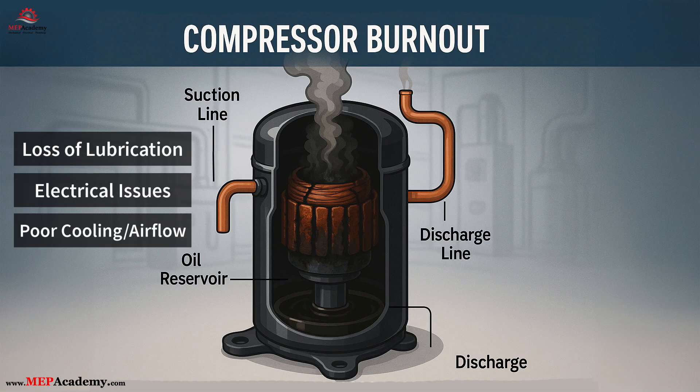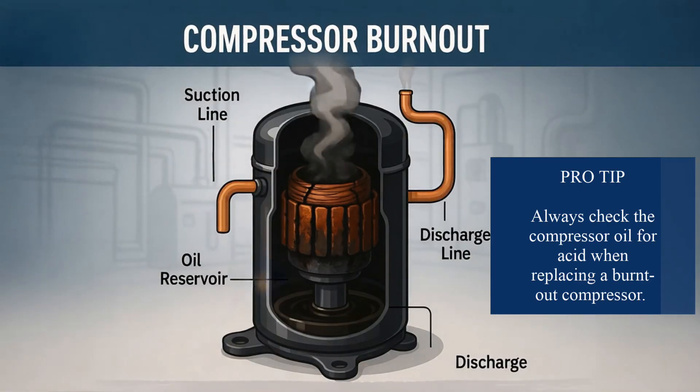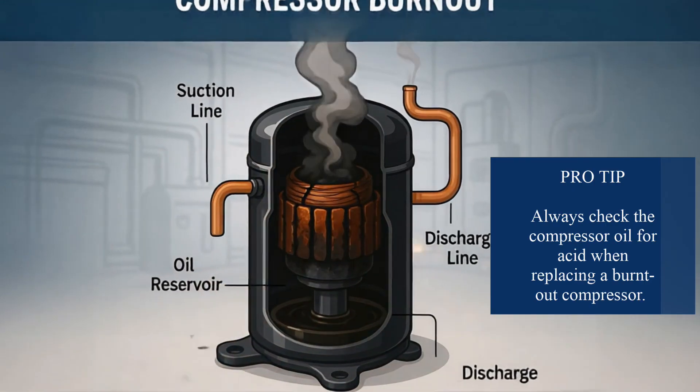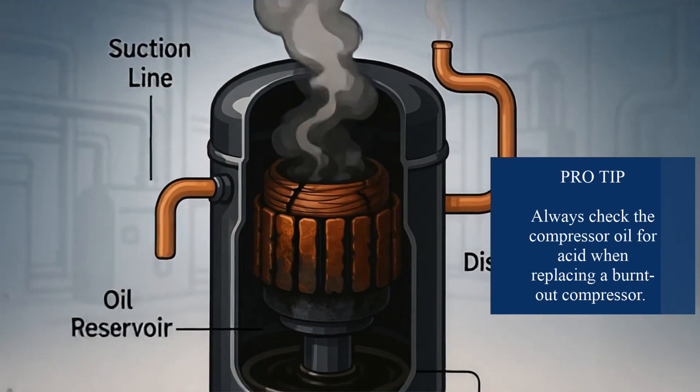Overheating due to poor cooling or airflow occurs when dirty condenser coils, blocked airflow, or failed condenser fans prevent proper heat rejection, causing the compressor to run hot and eventually fail. Pro tip: always check the compressor oil for acid when replacing a burnout compressor.